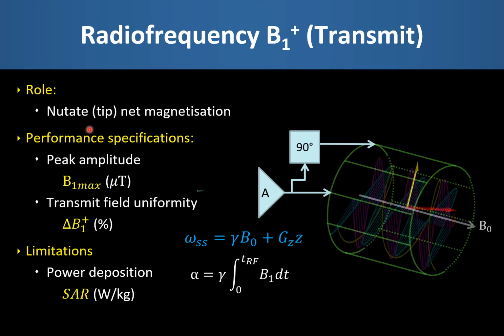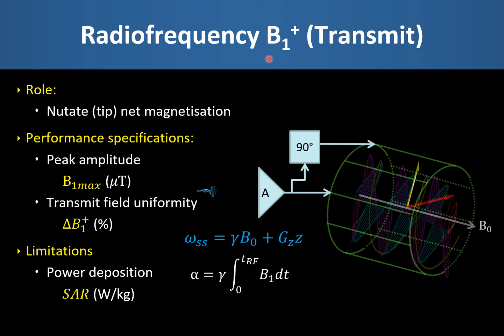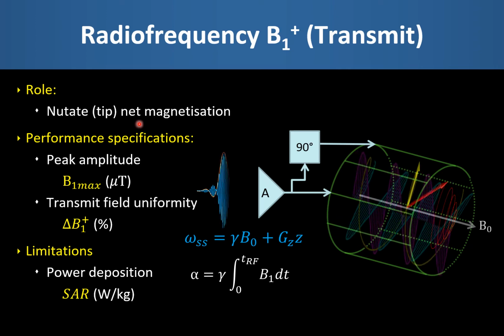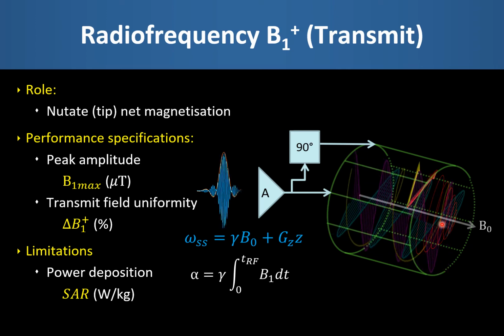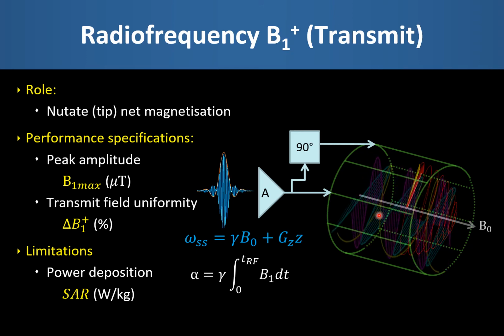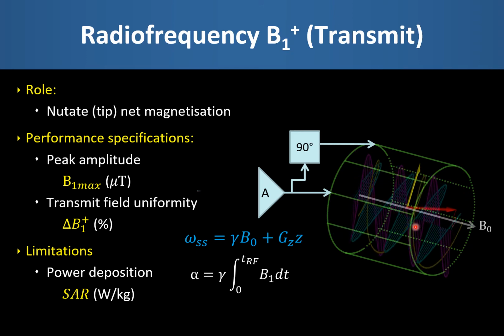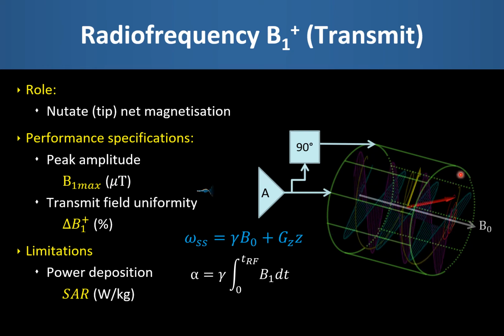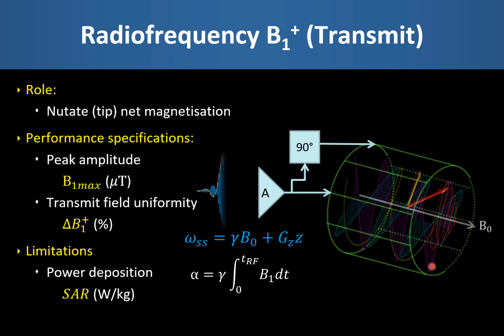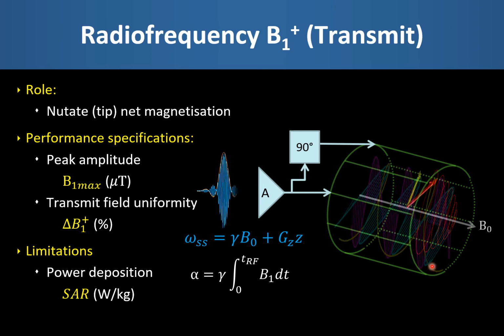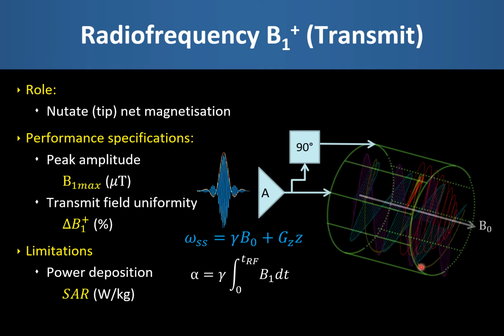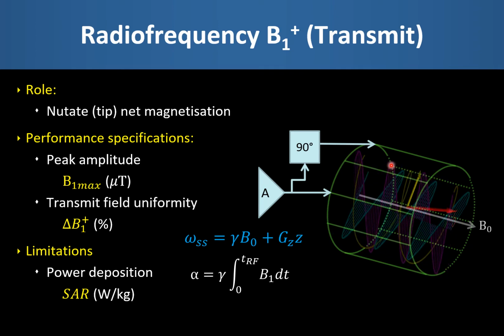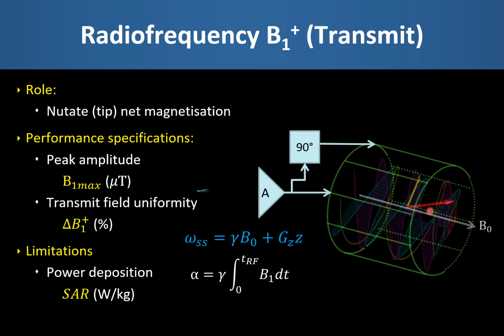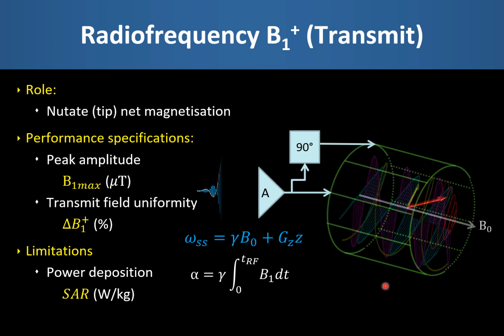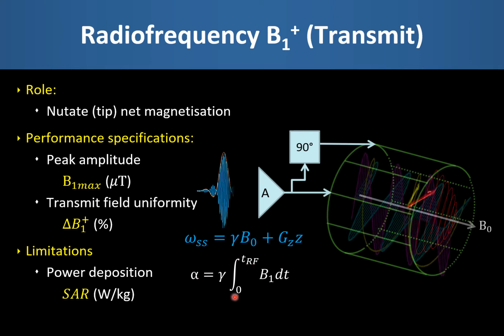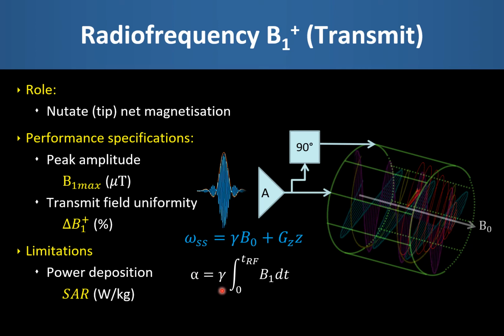The requirements of the RF transmit side, or B1 plus, is to nutate or tip the net magnetization. We establish a circularly polarized B1 field inside our birdcage coil, shown as the yellow arrow precessing in the laboratory frame of reference. Because that frequency is resonant with the precessional frequency of the nuclei at the desired slice location Z, then whilst the slice select gradient is applied, we can tip the net magnetization, the red arrow here, into the transverse plane. The nutation angle is given by the integral of the RF pulse envelope.